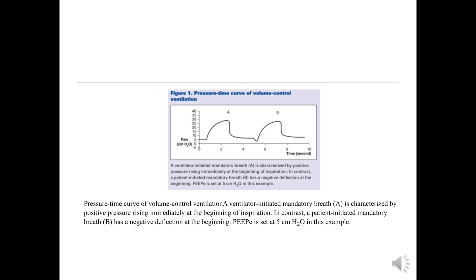Here you can see the pressure-time scalar of a volume control ventilation where pressure is plotted against time. The first breath labeled A is a ventilator-initiated mandatory breath, showing positive pressure rising immediately at the beginning. Breath B is a patient-triggered mandatory breath, depicted with a negative deflection at the beginning. The baseline pressure starts from 5, meaning the set PEEP is 5. From that point the pressure increases through inspiration, reaches a maximum, then decreases.